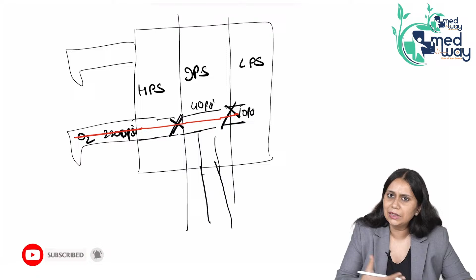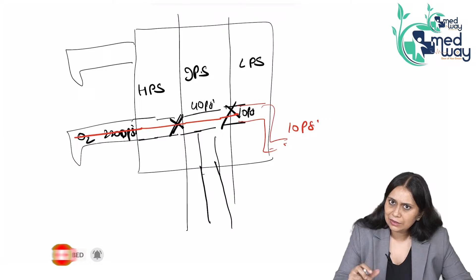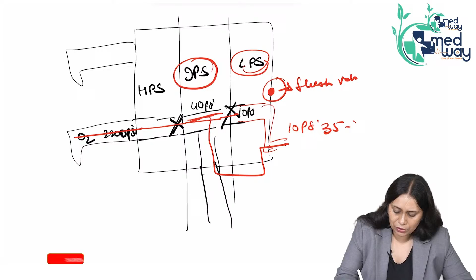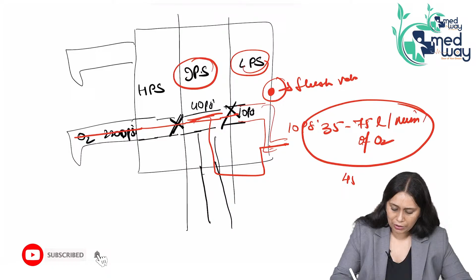We normally get gas coming out from the low pressure system at 10 psi. But there is a button in the machine, this is called the flush valve. When we press this button, it bypasses the low pressure system and brings the gas from the intermediate pressure system to the outlet. So, this button, emergency oxygen flush, comes under the intermediate pressure system. It does not pass through the low pressure system and it gives 35 to 75 liters per minute of oxygen per press at a pressure of 45 psi, right? So, this is your emergency oxygen flush.